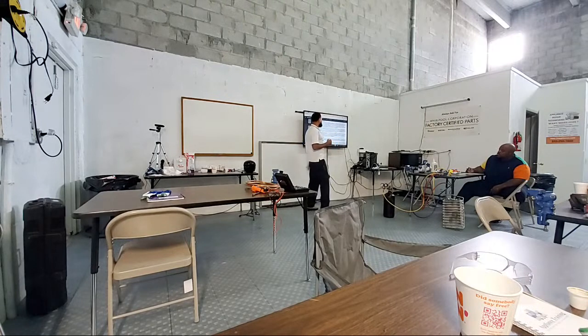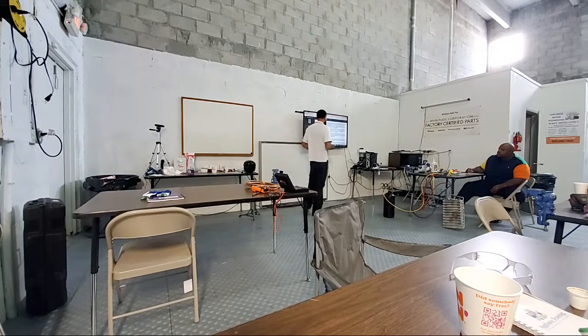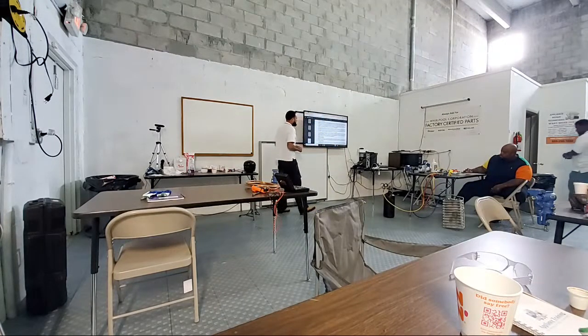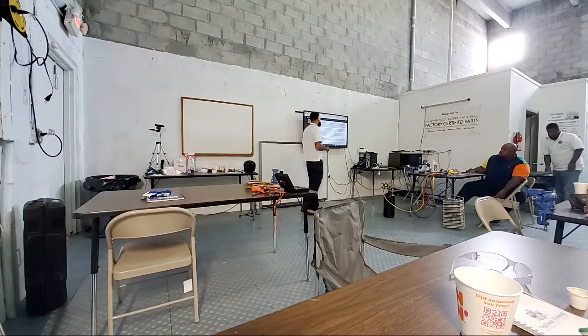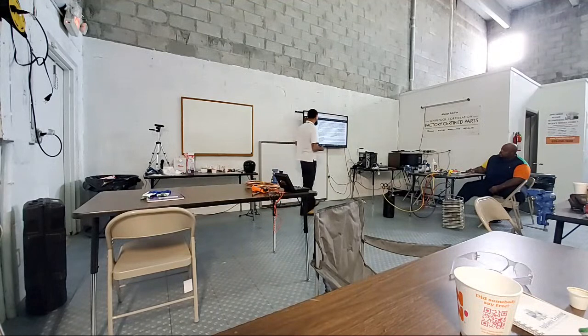Since the evaporator in the refrigerator/freezer is well below the freezing point of water, what's the freezing point of water? 32 degrees. Frost will form on the evaporator. With a plate style evaporator that relies on convection to maintain temperature, frost buildup affects the efficiency of heat removal, but will not prevent the system from maintaining temperature. The biggest issue is the loss of storage space as the thickness of the frost increases.